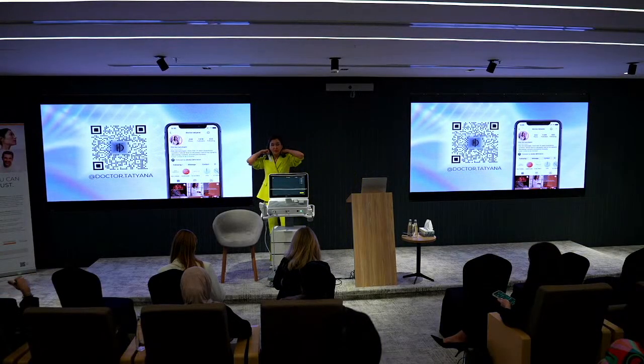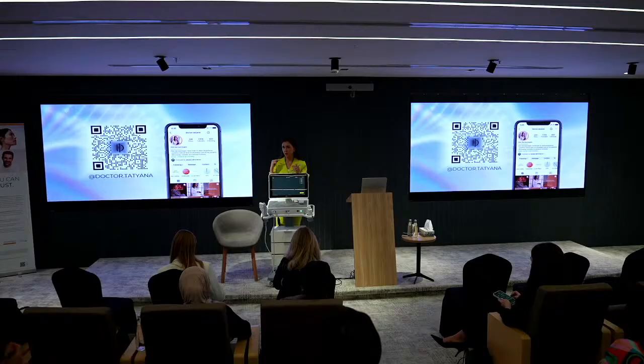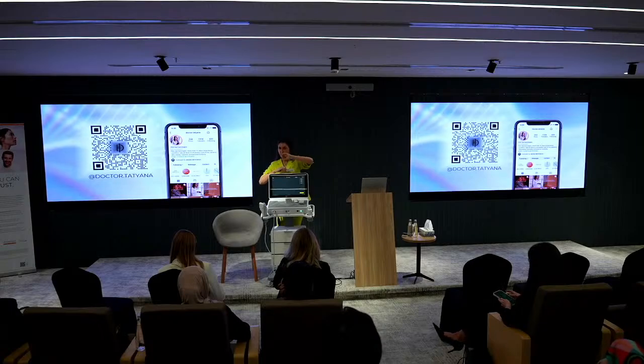Yeah, so definitely it will. It will, because in the areas where there are defects, you cannot guarantee that it's going to create exactly the thermal coagulation point, or that this point will be at the depth where you are looking for. So maybe the transducer is 4.5, but because of the defect, 1 or 3 thermal coagulation points will be more superficial or somewhere scattered, spread in the tissue. So try to teach your nurses to be super gentle with the membrane of transducers.